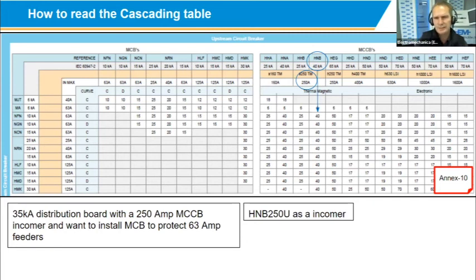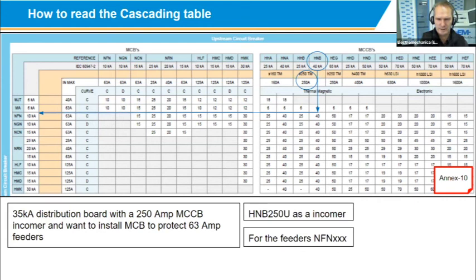I then draw a line downwards to see which other product can handle 40,000 amps when used in a cascaded system. So then go to the left and you will see, oh okay, so I can use an NFN 10 kA product. Awesome. Now this is a cascaded system. If you use an NFN 10 kA product underneath an HNB 250 in a 40 kA application, you will be safe in doing so, because these scenarios have been tested like this. And this is guaranteed by the manufacturer that you can use it in this specific application.